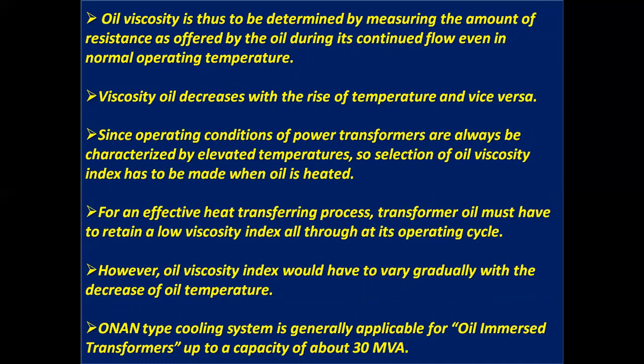Viscosity of the oil decreases with the rise of temperature and vice versa. Since operating conditions of power transformers are always characterized by elevated temperatures, the selection of oil viscosity index has to be made when the oil is heated. For an effective heat transferring process, transformer oil must retain a low viscosity index throughout its operating cycle. However, oil viscosity index varies gradually with the decrease of oil temperature. ONAN type cooling system is generally applicable for oil-immersed transformers up to a capacity of about 30 MVA.